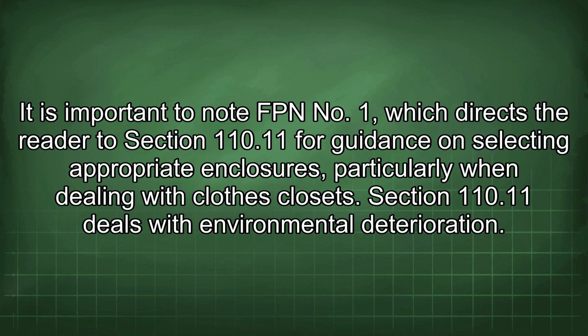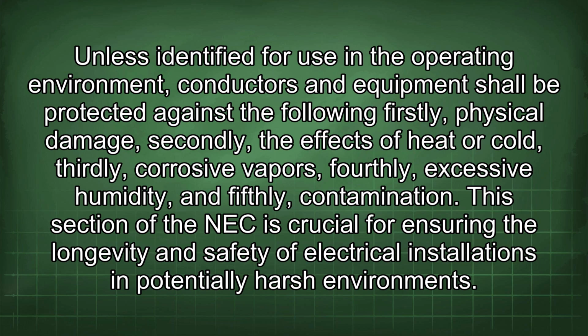It is important to note FPN No. 1, which directs the reader to Section 110.11 for guidance on selecting appropriate enclosures, particularly when dealing with clothes closets. Section 110.11 deals with environmental deterioration. Unless identified for use in the operating environment, conductors and equipment shall be protected against the following: firstly, physical damage; secondly, the effects of heat or cold; thirdly, corrosive vapors; fourthly, excessive humidity; and fifthly, contamination. This section of the NEC is crucial for ensuring the longevity and safety of electrical installations in potentially harsh environments.